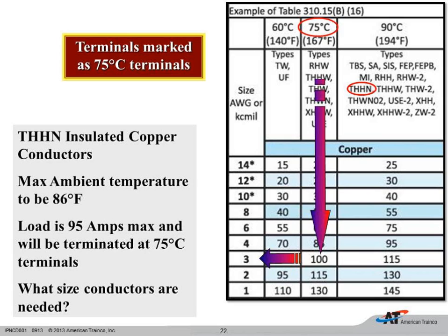So we have to understand that the terminals play a very important role in determining the size of our wire. If our terminals are marked at 75 degrees Celsius, then we can go ahead and use that column that is 75 degrees Celsius. That's no problem. But let's say that we had conductors that were THHN, which the slide is showing us. If we have THHN conductors, that would lead us over here to the 90 degrees Celsius column, but our terminals are only rated at 75, so we are only as strong as our weakest link. Even though THHN wire is being used on this circuit, we would have to come back to the 75 degrees Celsius column. We need 95 amps. We would have to come down to the number that's either 95 or the one closest to 95, and come over and see that we have a conductor size of 3 gauge.